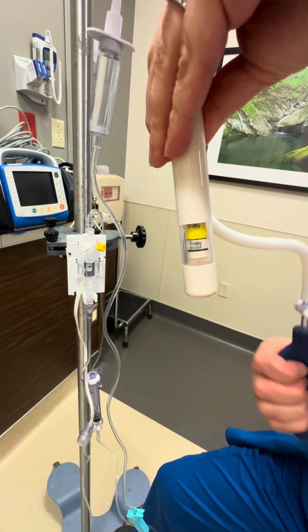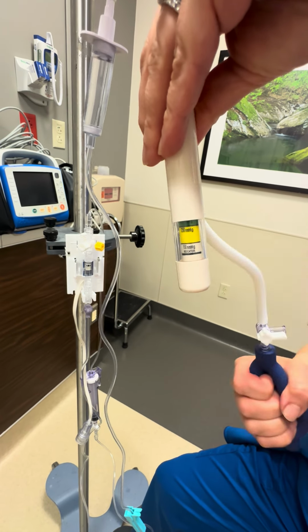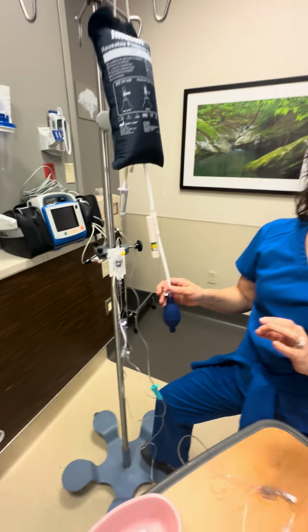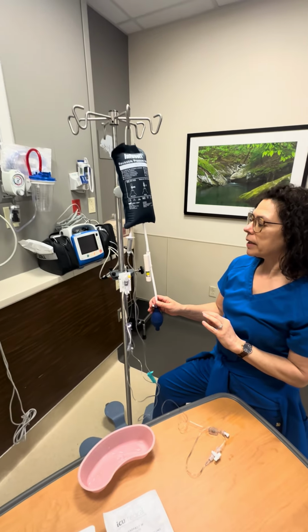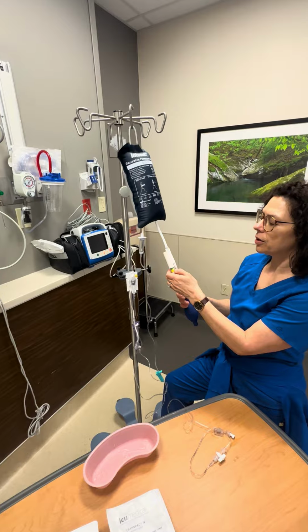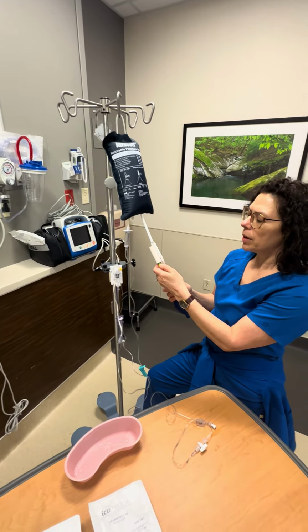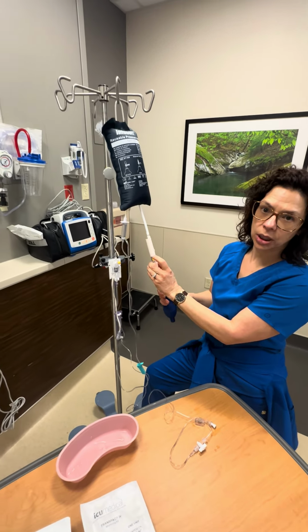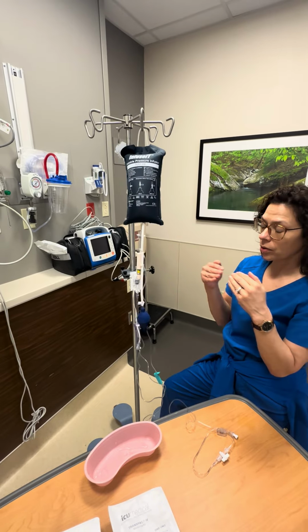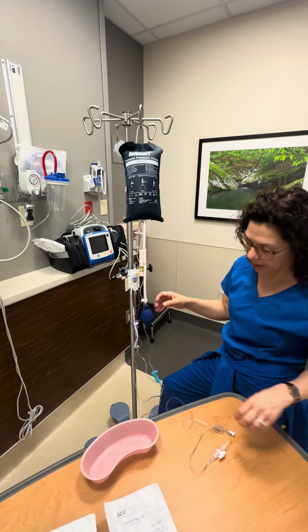Okay, there's the yellow. And you want to go to green. So once you're at green, you're good. If you are having any trouble with your art line, the first thing to check is to make sure that you're at 300 millimeters of mercury of pressure. That's how much pressure that you need in order to combat against the arterial flow to get a reading.